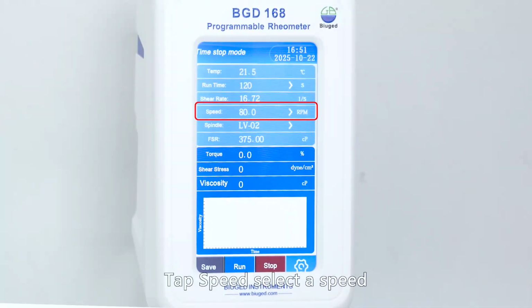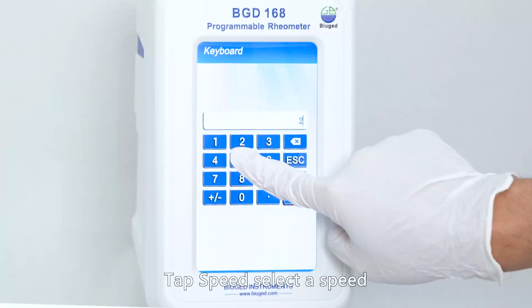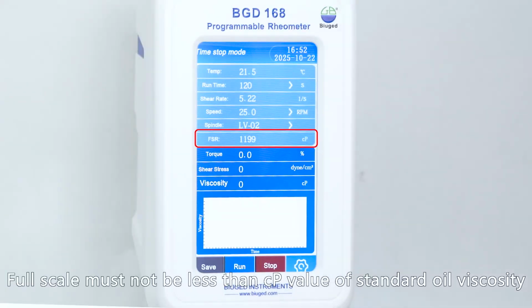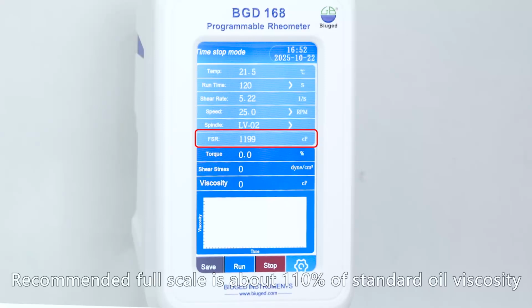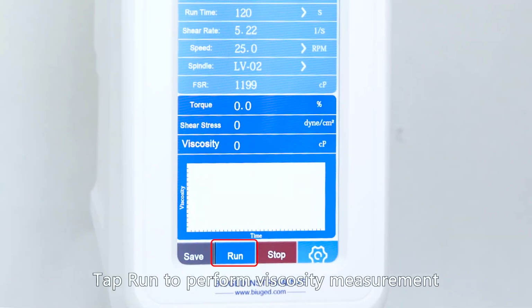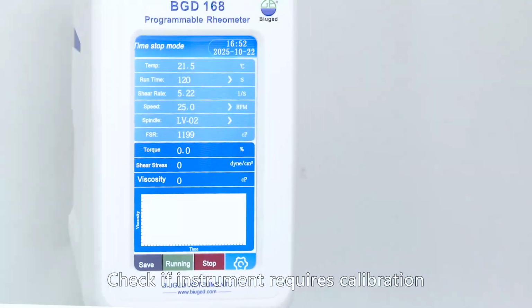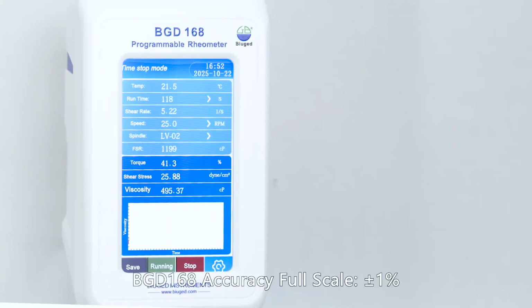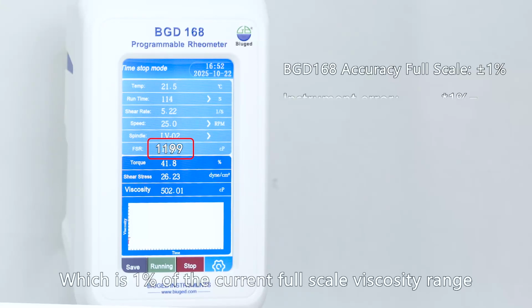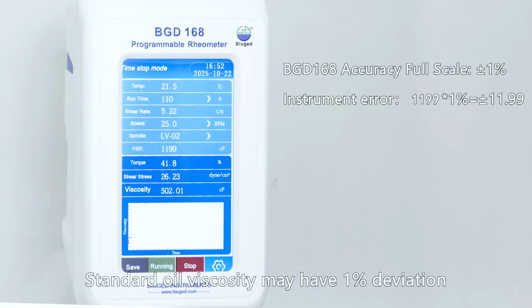Tap speed, select a speed. Full scale must not be less than CP value of standard oil viscosity. Recommended full scale is about 110% of standard oil viscosity. Tap run to perform viscosity measurement. Check if instrument requires calibration. BGD 168 accuracy is plus or minus 1% of full scale, which is 1% of the current full scale viscosity range. Standard oil viscosity may have 1% deviation.